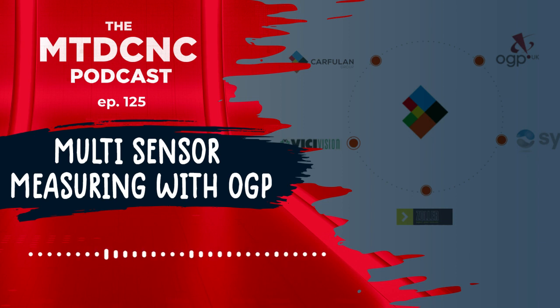So the VICI Vision product measures cylindrical and non-cylindrical components with telecentric optics, checking the outside profile of the component to start off with. It will then do rotational scans to give you things like run out. So it's a 3D, 2D type optical system that can measure small pins less than a millimeter, up to 240 millimeters in diameter, and an overall length up to 1250mm. There's a good selection of machines available for different industries.